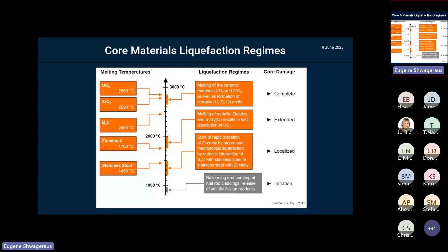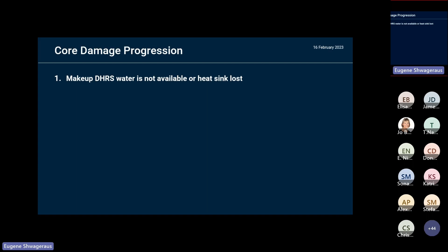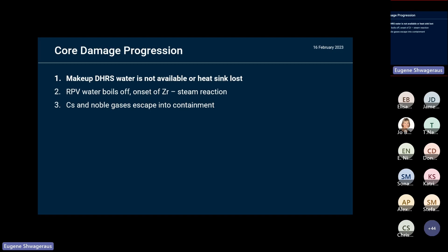If the decay heat removal systems don't work as we postulated, so no power to pumps to circulate that water, and/or the heat sink water is not available -- these cooling ponds with sprinklers, there are many, but they no longer have enough cooling water -- then the pressure vessel water gets to saturation and starts boiling, the zirconium-steam reaction occurs, cesium and noble gases escape, and the core goes down into the lower part of the pressure vessel.